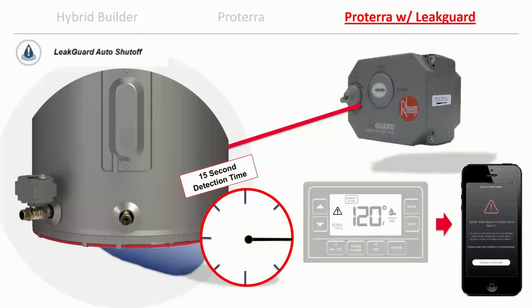If you detect a leak on this, let's say it wasn't a leak from the heater, it was a leak from something else, or you got a false negative because somebody sprayed water into the pan or spilled water into the pan, all you have to do is hit a button on the controller. It's going to override the alarm, bypass the shutoff, and open the valve back up. That override will last 24 hours, and that gives the wick time to dry out. It's not a one and done leak sense. This leak sense works forever, really. Once it dries out, it kicks back on, and it's looking for the next leak.